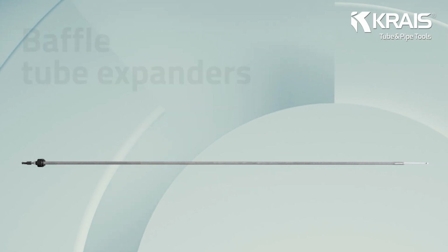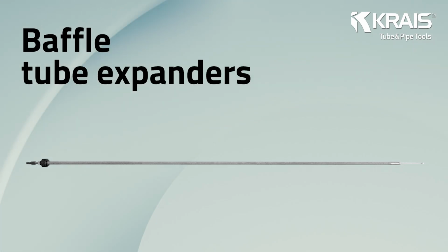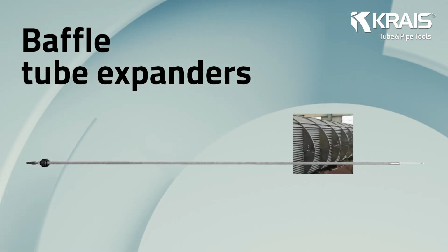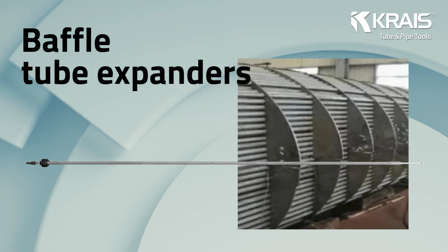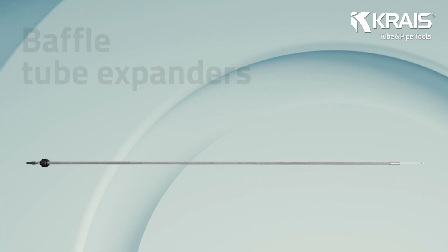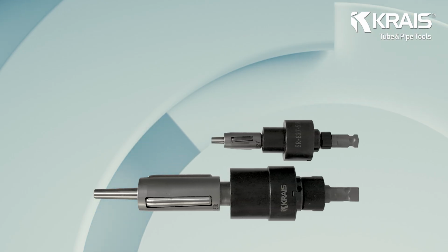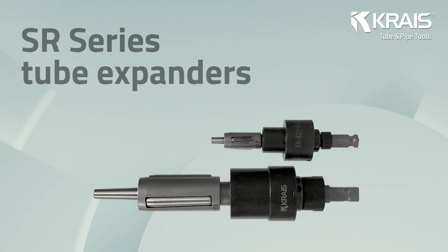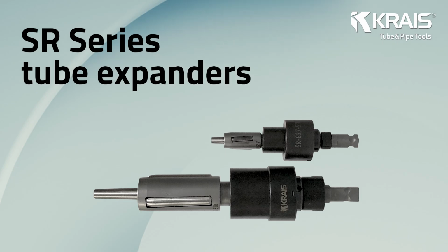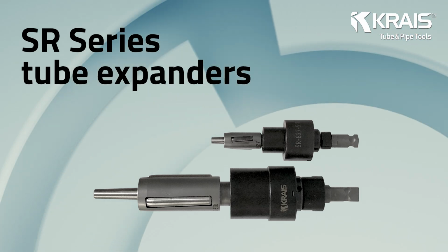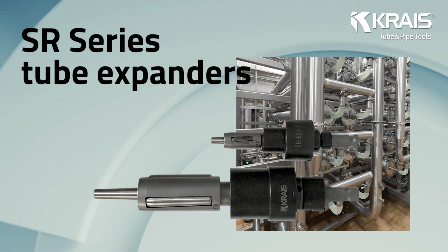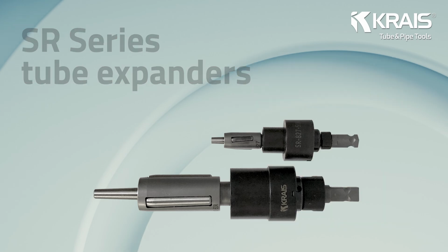KRAIS baffle tube expanders are long-reach tools for rolling on internal support plates, not only at the tube sheet, but also at support sheets or baffles deeper inside the bundle. SR refers to short-reach solutions used where geometry limits stroke, bends, U-tubes, or very short straight sections. OD range depends on the ordered configuration.